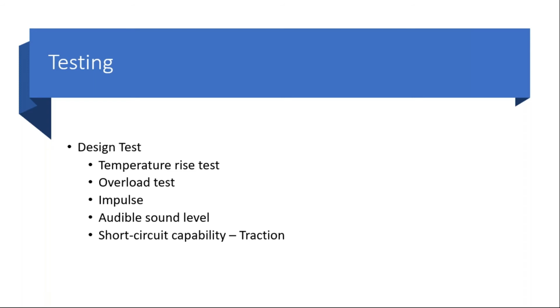Temperature rise test. If we have just simple ONAN and ONAF ratings, then since we have multiple windings, shutdowns need to be taken to determine the temperature rises. Whereas when we say overload test, which actually may not be exactly overload, but it is based on the traction duty, we have to do the extra test for maybe 2 hours based on the cycles, which is commonly done by equivalent rating for, for instance, extra heavy duty transformers. It is 160.3%, as I mentioned earlier.